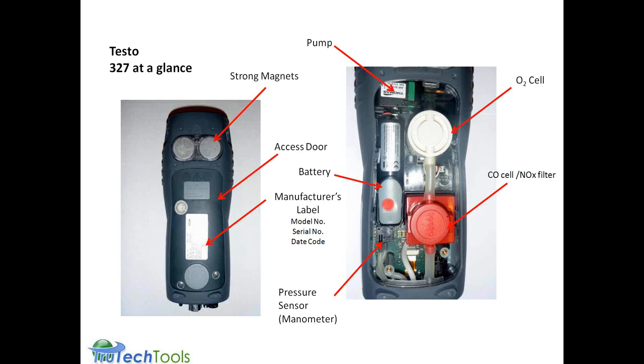But the battery, you push your thumb in the slot here where the arrow is and then slide down, it would release the contacts of the battery. To put it back in, you lay it in the tray and push it upward to lock it back in place. Pressure sensor is here just for reference. There's usually no need to service or do anything with the pressure sensor. The oxygen sensor here is a white sensor at the top. That is one of the replaceable or user serviceable sensors. It's got a simple plug you can see just behind it here. It's a little connector. You may need needle nose pliers to pull it out, but you want to make sure that you hook it back up from the outlet of the pump.